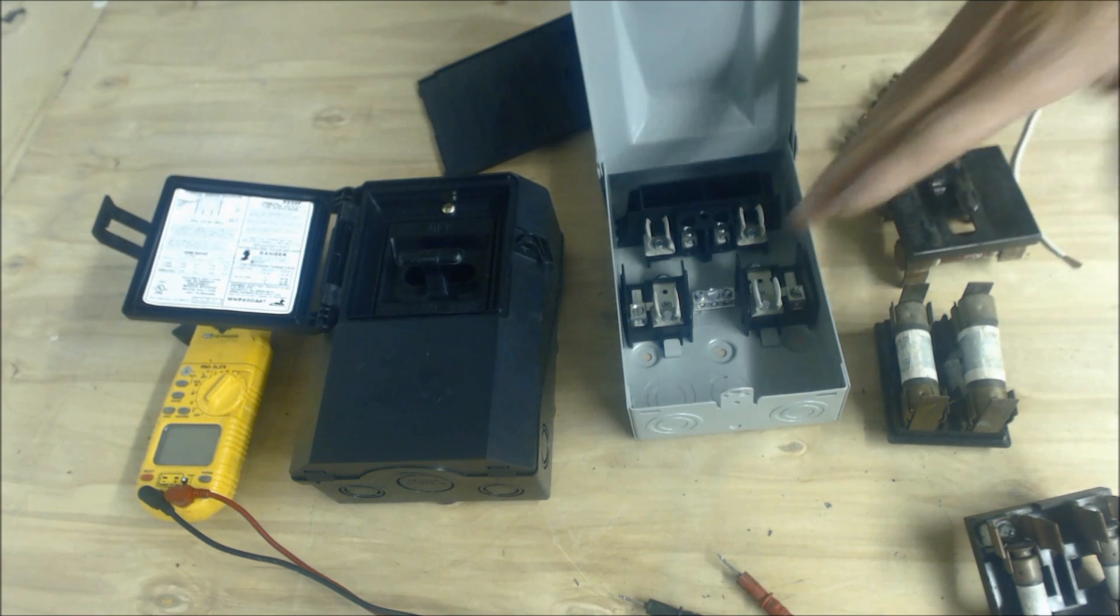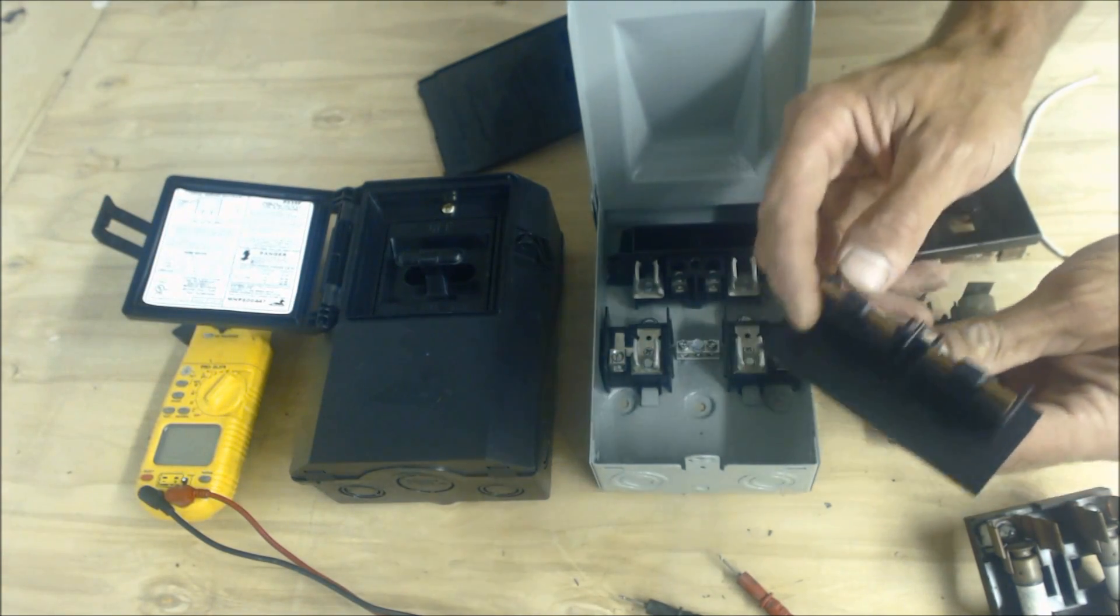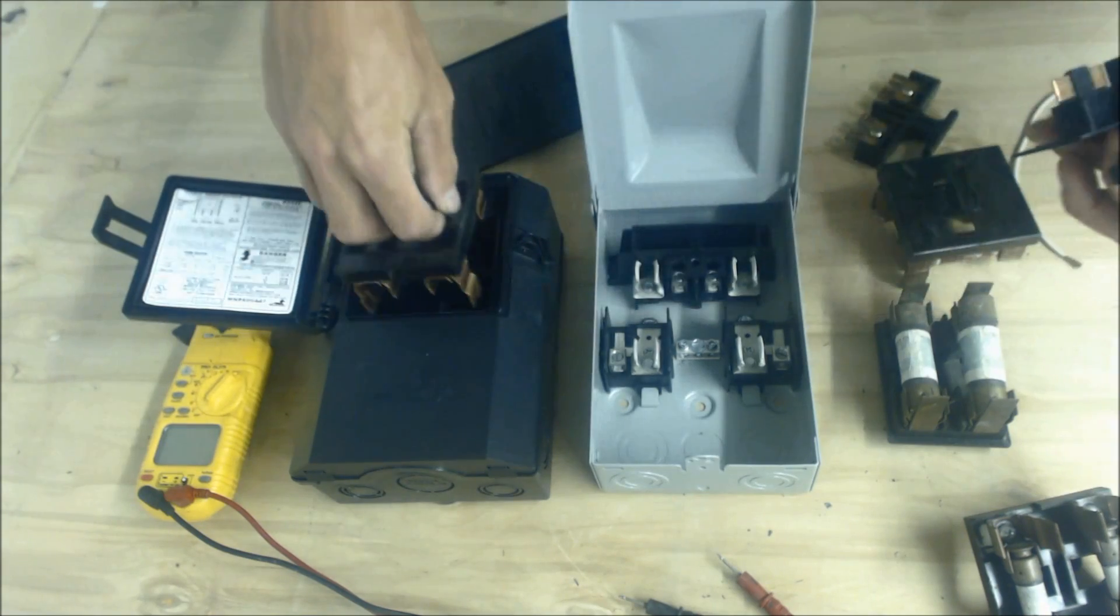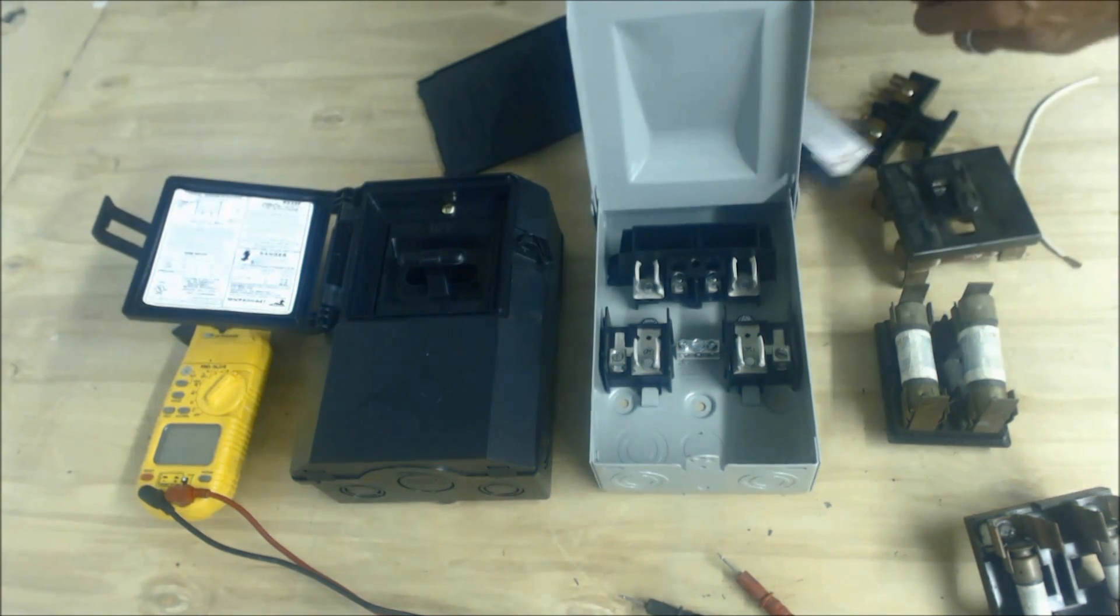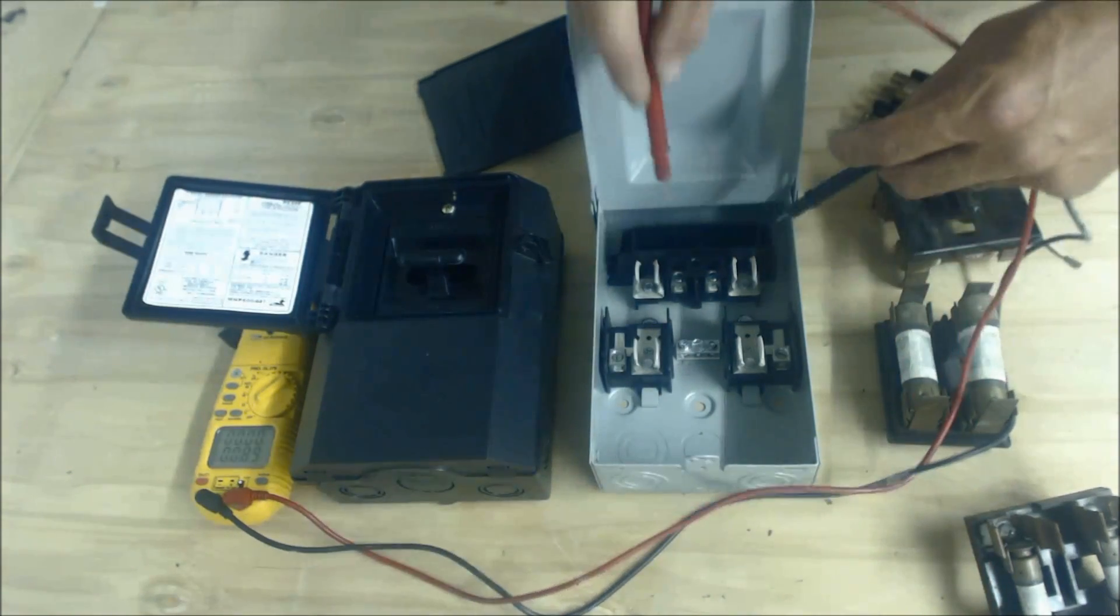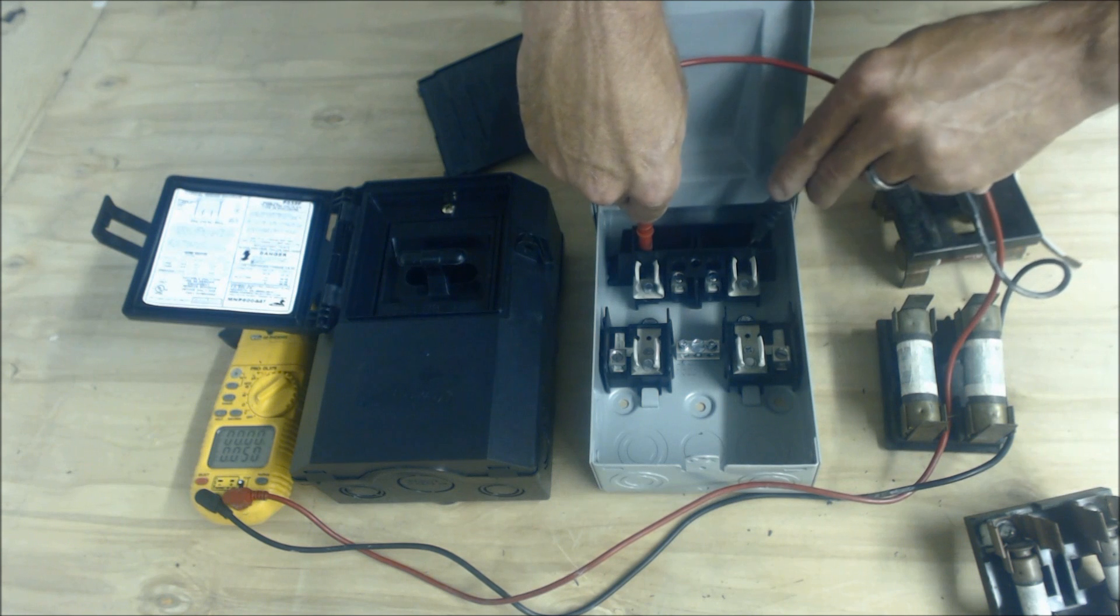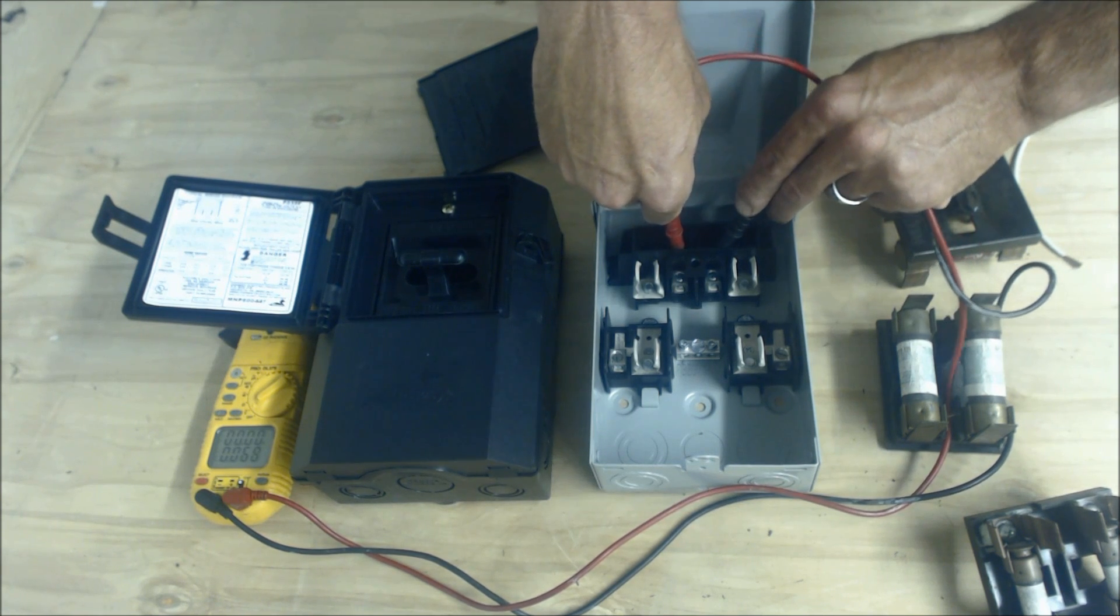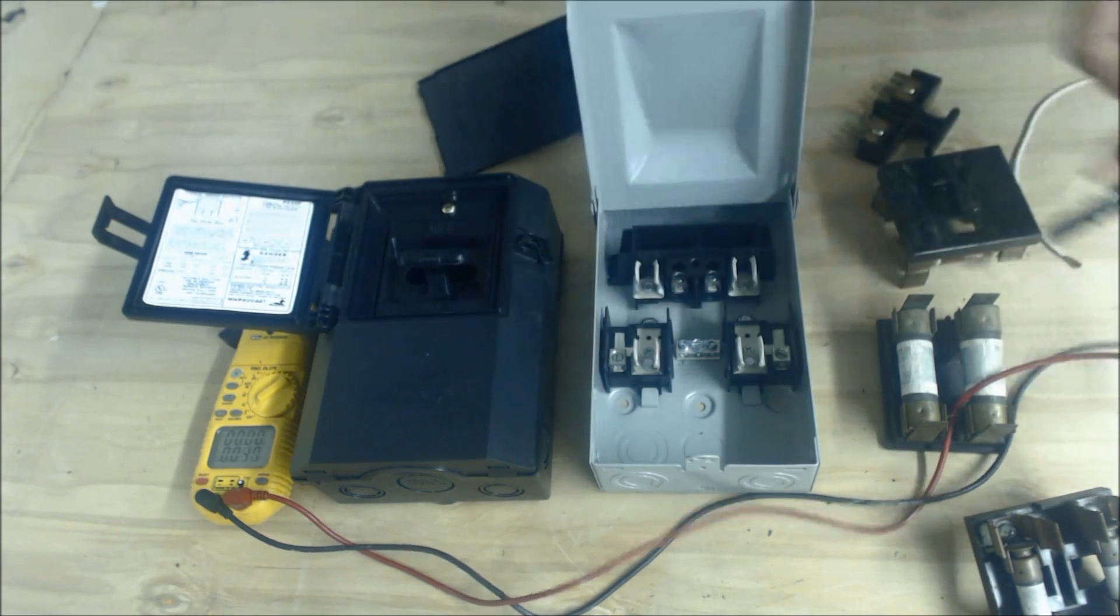So as far as testing for voltage on these, what you can do is you want to look at your disconnect handle. So what we're doing is we're actually connecting this and this on this particular one, versus here, you're connecting the top and bottom. So without taking the cover off, you're going to need to try to figure out which ones are the voltage and which ones are not the voltage. So what I'm doing is I'm just going to take the multimeter, on V for volts AC, and I'm going to come right into here, and what I'll do is I'll take this one and this one first. I'll see if I have 240 volts, then I'll take the outside ones. Do I have 240 volts? Then I'll take this one. Do I have 240 volts? And by then, if you don't have 240 volts, then you know that something before this portion is stopping it. In this case, it could be the fuses.